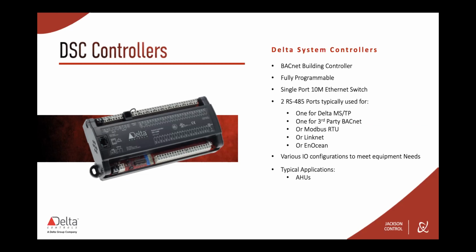Again, with 2 RS-485 ports, so got a few different options now in the DSC product line, just because it's geared more towards air handlers. So typically one would be used for MSTP, one would maybe be for a third-party BACnet MSTP, because we'd like to suggest breaking up the networks if possible. You'll have Delta on one side, this is easier to manage. Have third-party stuff like VFDs or whatever it may be on a second port, if at all possible.